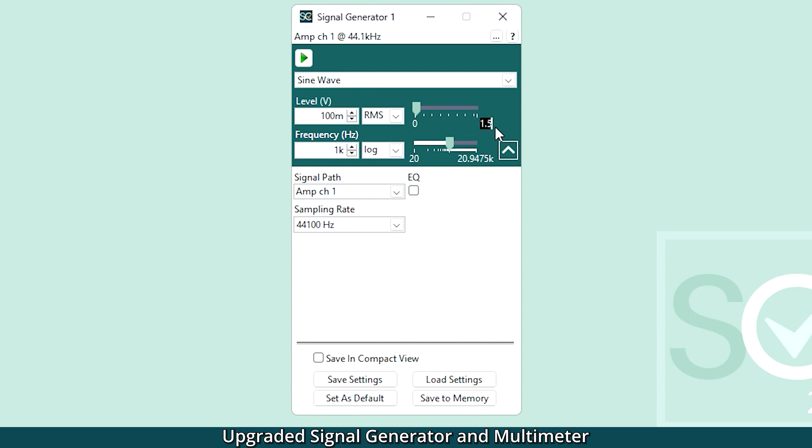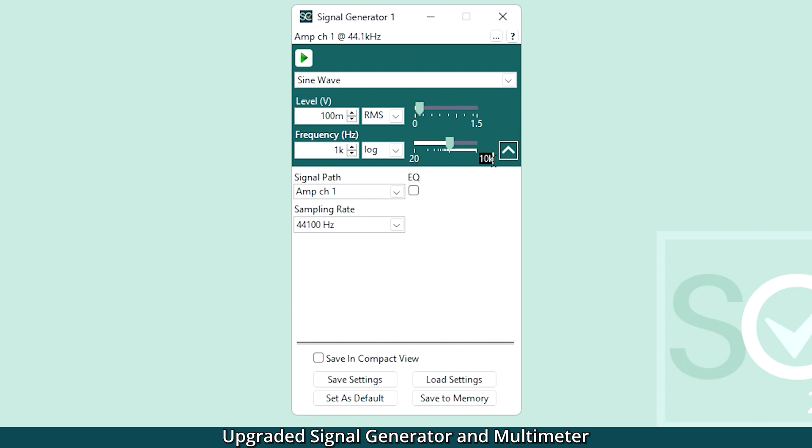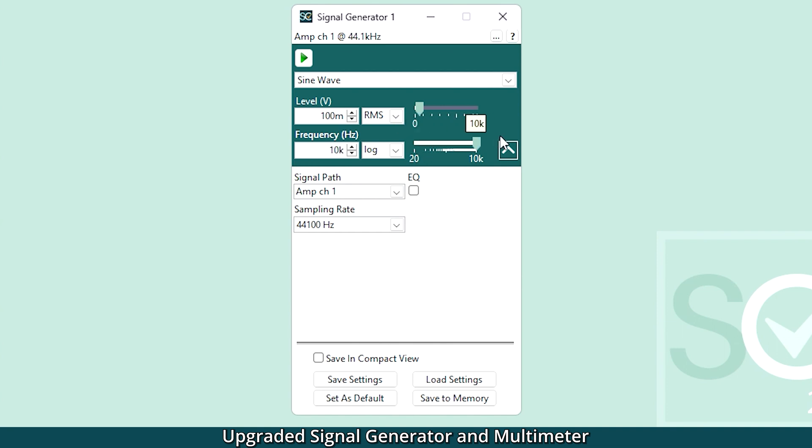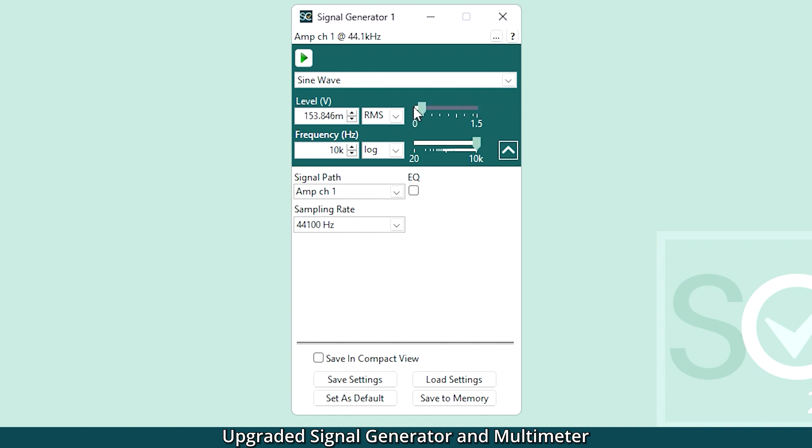We've also added functionality for audio signal playback. You can now set maximum and minimum output levels and frequencies in the signal generator to limit the range of the signal path. This prevents accidental equipment damage, for example, accidentally playing a very high-level signal through a speaker or artificial mouth. These levels are retained when the configuration is saved or used in a sequence, but levels can still be manually adjusted within these ranges.